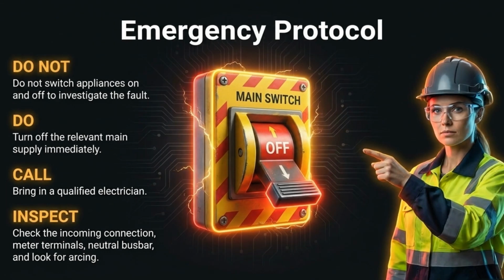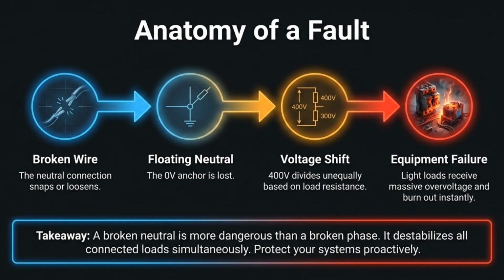If you suspect a fault, do not toggle your appliances. Turn off the main power immediately and contact a qualified electrician to inspect the system. To summarize, a broken neutral causes an unstable voltage shift that can destroy equipment and create severe safety hazards. Always ensure your system has proper, proactive protection.